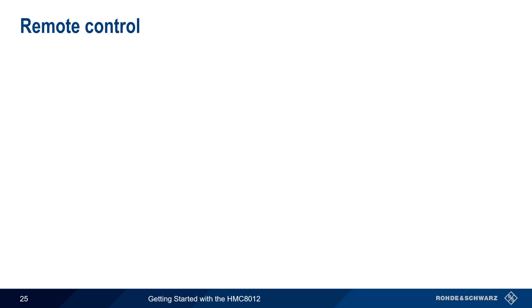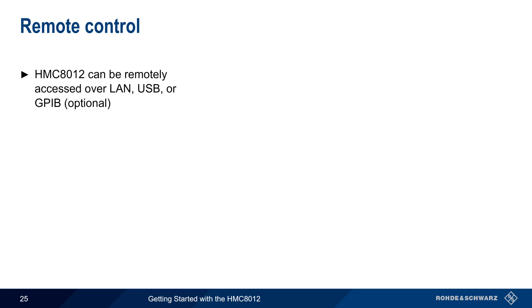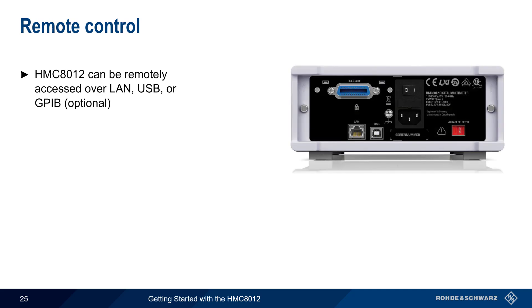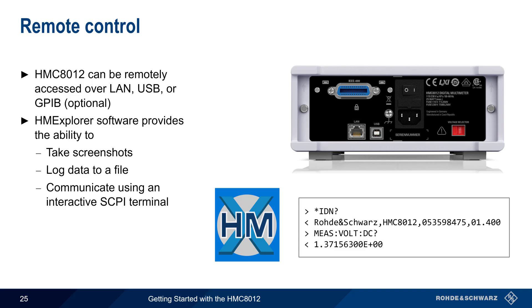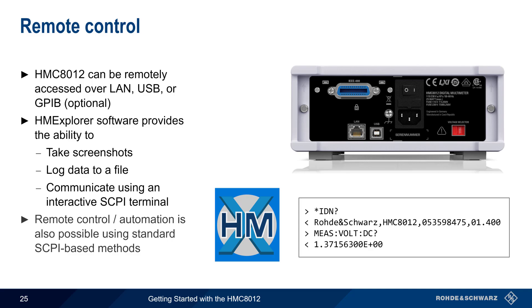Our final topic is remote control. The HMC 8012 can be remotely controlled over LAN, USB, or an optional GPIB interface, all of which are located on the rear panel of the instrument. The easiest way to interface with the HMC is using the free HMExplorer software package, which provides a graphical user interface for common tasks such as taking screenshots, logging data to a file, and communicating with or controlling the instrument via an interactive SCPI terminal. The HMC also supports remote control and automation using standard SCPI-based methods; please see the programming guide for more detailed information.